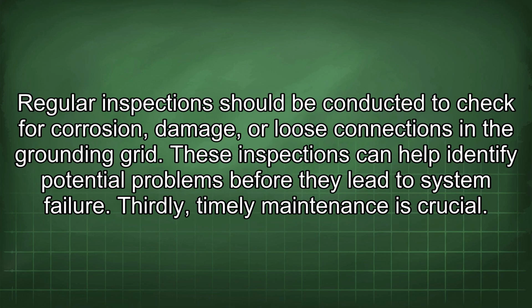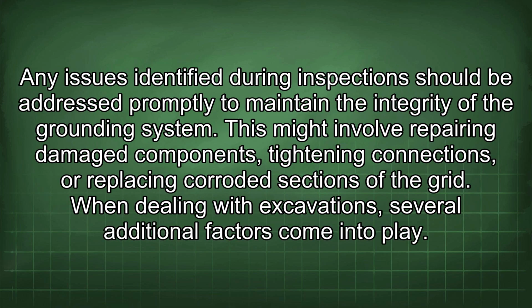Regular inspections should be conducted to check for corrosion, damage, or loose connections in the grounding grid. These inspections can help identify potential problems before they lead to system failure. Thirdly, timely maintenance is crucial. Any issues identified during inspection should be addressed promptly to maintain the integrity of the grounding system. This might involve repairing damaged components, tightening connections, or replacing corroded sections of the grid.